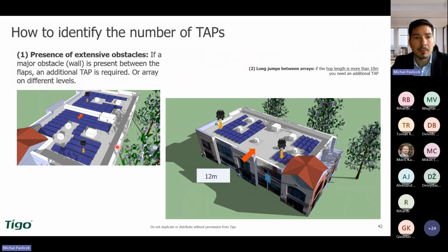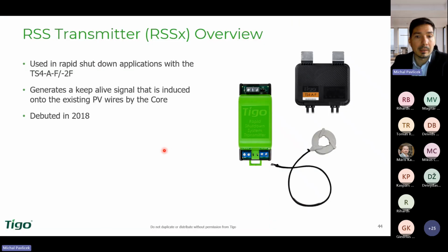If you have such cases on the rooftops, if there is a barrier, unfortunately some kinds of barriers do not allow the wireless communication to go through. So then maybe you would need 2 taps here. Same if on the rooftop the distance between 2 strings or 2 optimizers is more than 10 meters from each other, again 2 taps are needed. If, for instance, in another project the modules were only 3 meters apart, you don't need it, because the optimizer works as a repeater. That optimizer will repeat the signal to the next one as long as they are closer than 10 meters to each other. A very robust and easy solution.